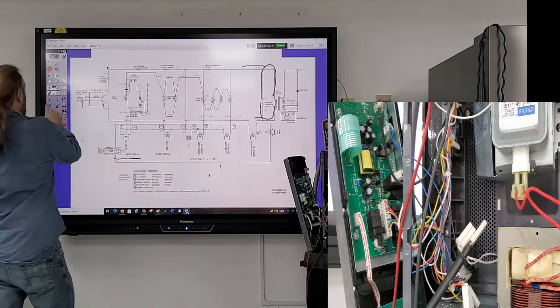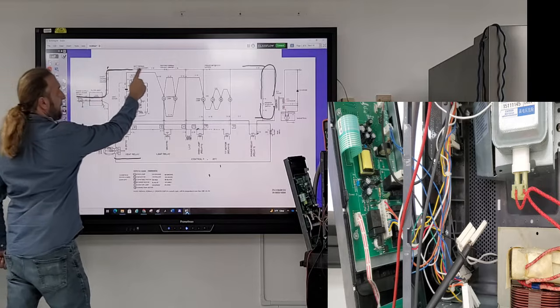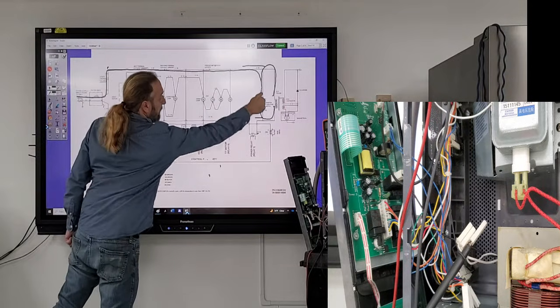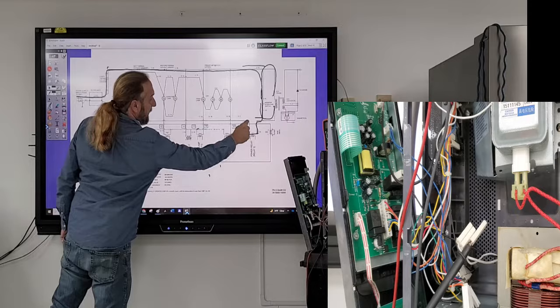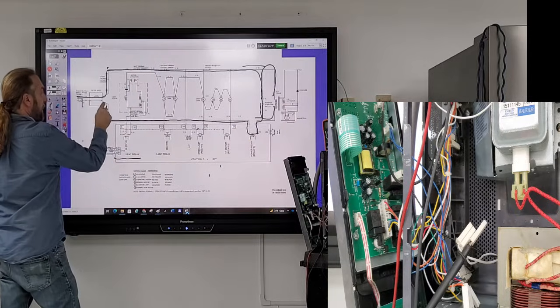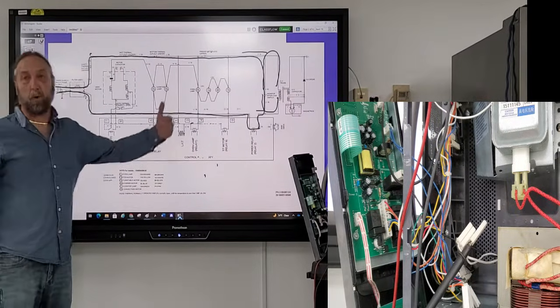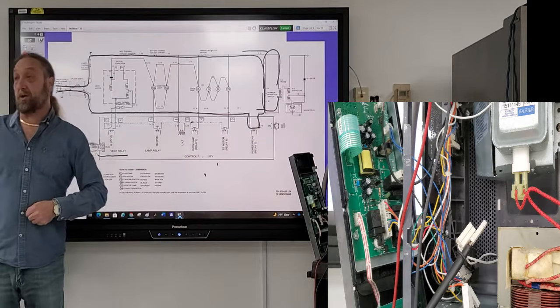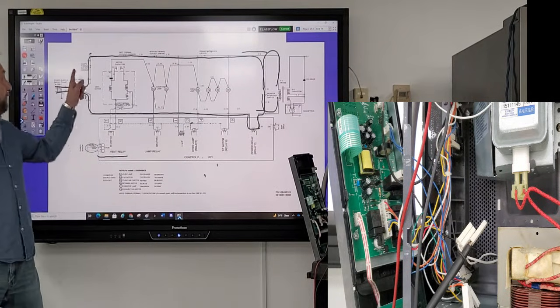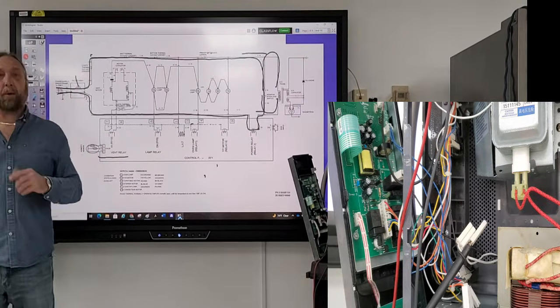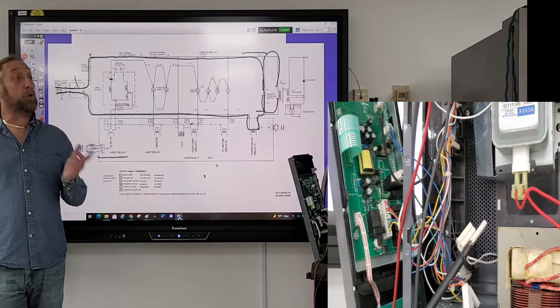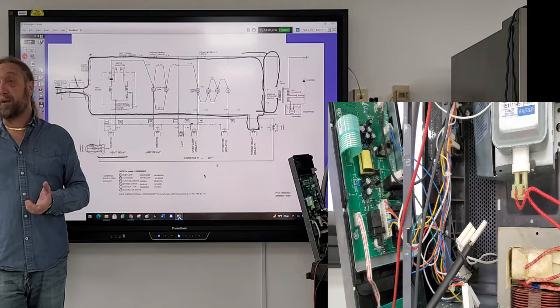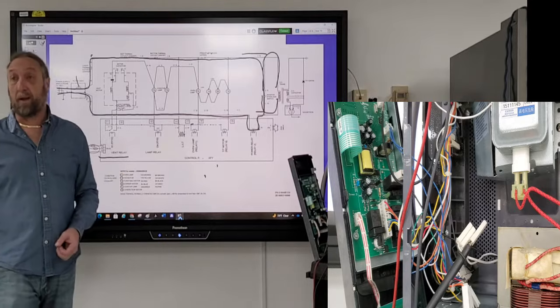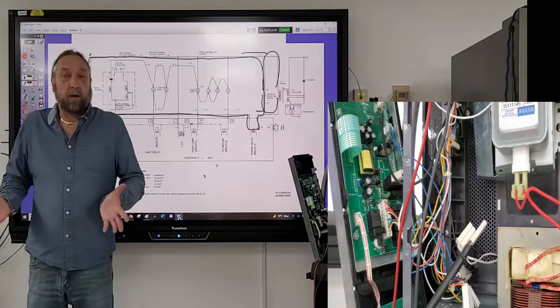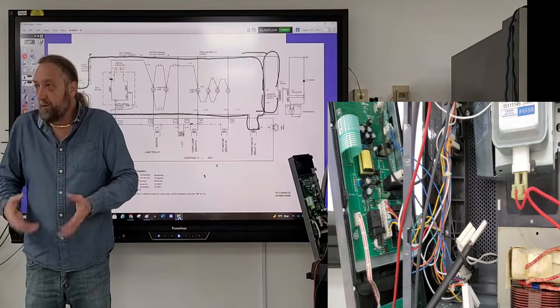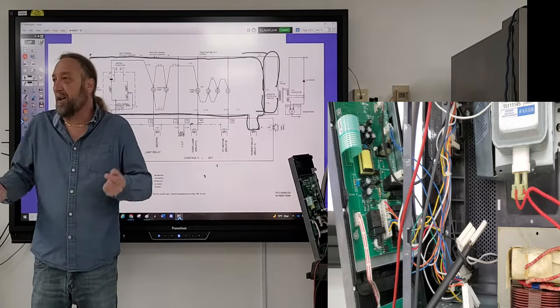Okay, if power goes through that door switch and goes through the monitor switch and through the relay, there's no load, like fan load or whatever, in that circuit I just drew. It's going to blow the fuse right here. And that manufacturer has a lot of fuses blown. Usually, when that happens, you ask the customer, was it running? You know how you guys are, you younger guys grew up and everything's fast, everything's done.